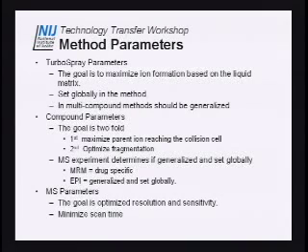The MS parameters, we're really talking about product ion scanning here. The goal is to optimize resolution and sensitivity and minimize scan time. Remember, the cycle time for the MRM is about 2 seconds. It takes 2 seconds to go all the way through, and then it takes about another second to do the product ion scan in the system we have set up.